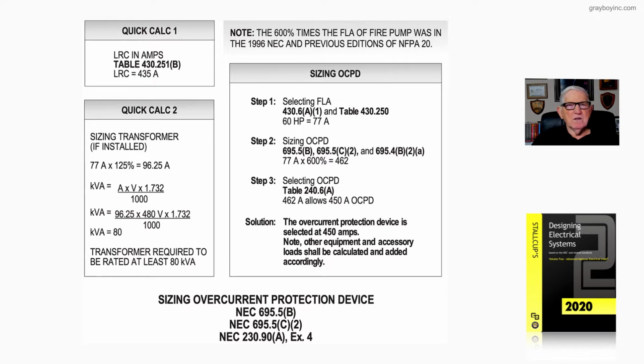But notice a quick calc one for this example is the locked rotor current in amps. Table 430.251(B) would list the starting current of these motors and locked rotor current of these motors based upon the design of the fire pump, whether it would be B, C, D, whatever it may be.